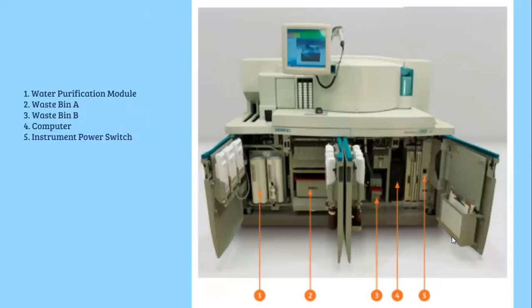In the little doors below is where a lot of our water reagents are, along with our wastes. Before we do QC, we're going to remove waste A and waste B. Those are labeled at number 2 and 3 below. And then once a week, we will be shutting down the system completely when we do QC, and that would be number 5. We just flip that power switch, let the machine sit for 5 minutes, and then turn it back on before the machine goes into downtime.